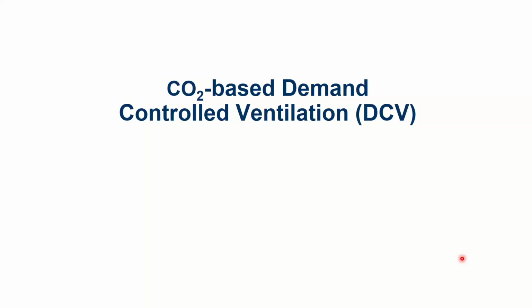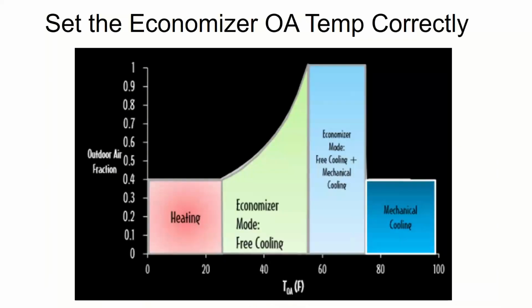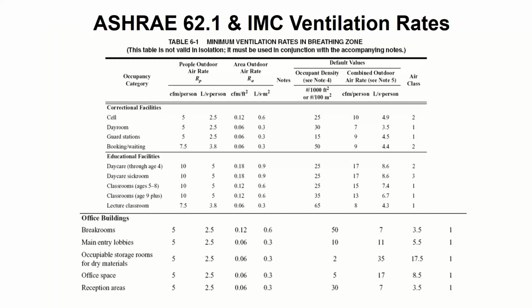Now, over ventilating has benefits, but there's also cons, which is energy consumption and humidity control. So normally in a non-COVID year, I'd want to bring in the ventilation air from this table, right? But if only half the people show up to work, maybe I can bring in half of the amount of the people portion of the ventilation, right? I'm bringing in 5 CFM per person for 100 people. Well, if only 50 are there, shouldn't I be able to take 50 times 5 and not bring that in?